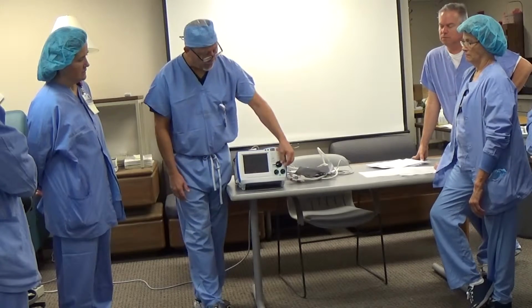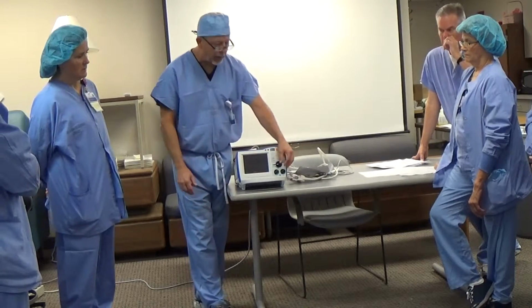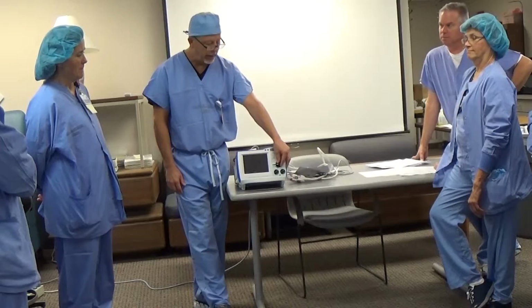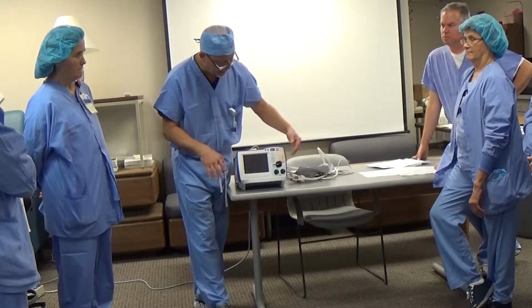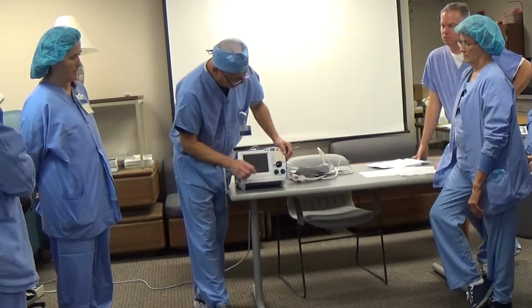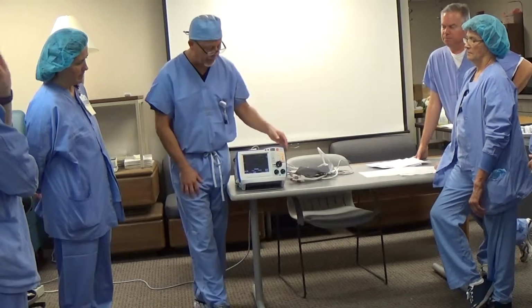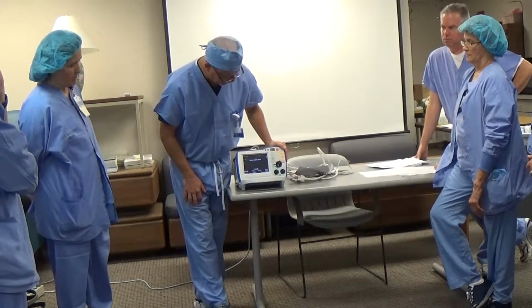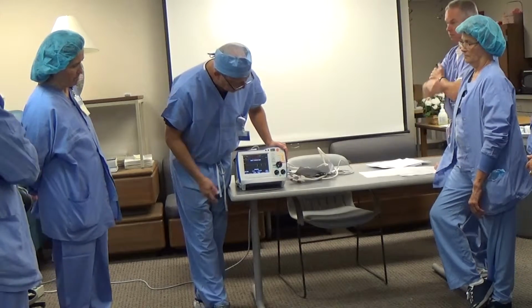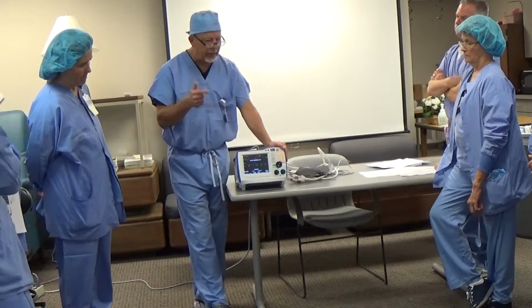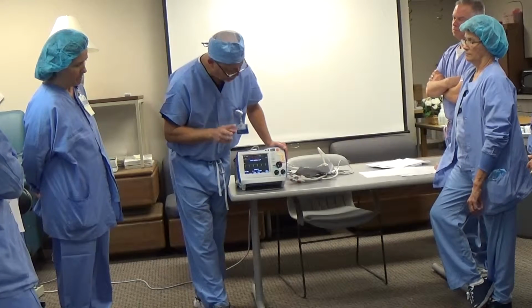Okay, so if we come in and we find somebody with a heart rate of about 20, and they want you to externally pace, the pacer part down here is in the green, and you would just turn it here, and once again, it will analyze your rhythm for you. Now, there's two things you have to do: your milliamps, your output, and your rate.